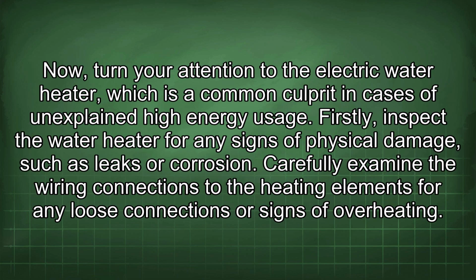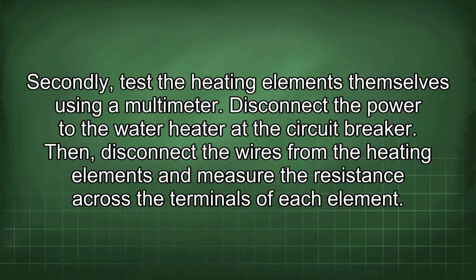Now turn your attention to the electric water heater, which is a common culprit in cases of unexplained high energy usage. Firstly, inspect the water heater for any signs of physical damage, such as leaks or corrosion. Carefully examine the wiring connections to the heating elements for any loose connections or signs of overheating. Secondly, test the heating elements themselves using a multimeter. Disconnect the power to the water heater at the circuit breaker. Then, disconnect the wires from the heating elements and measure the resistance across the terminals of each element.